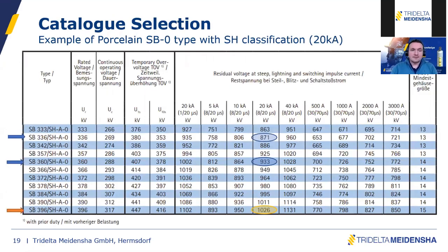Okay, so once you have defined the minimum UC, MCOV, and minimum rated voltage, it's quite common to select standard ratings from arrester manufacturers, and it's also standard to use rated voltages that can be divided by 3. So you can see here from our porcelain SB0 type catalog, I have selected some examples for 420 kV. Here we have 336 kV, it's a possibility. And here we have 360 kV. And here I also selected this one because I would like to show you what is happening if you are taking a surge arrester with a very high rated voltage.